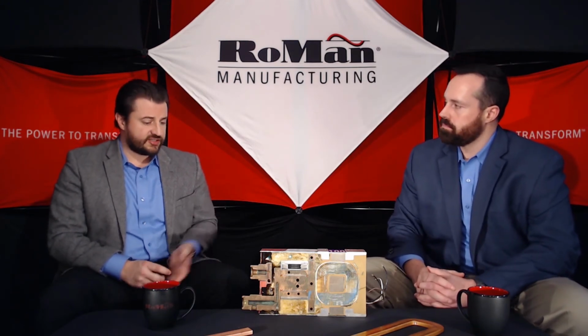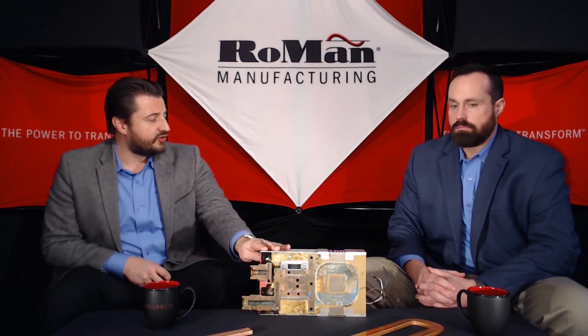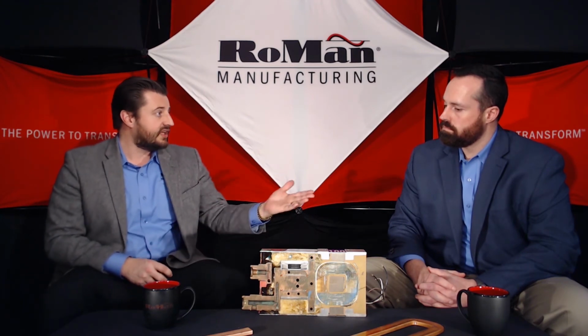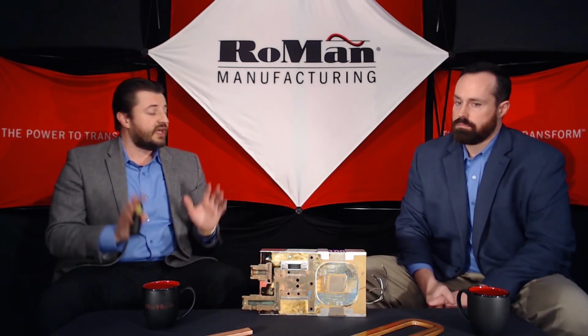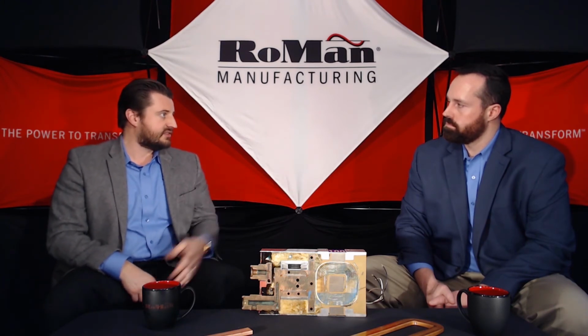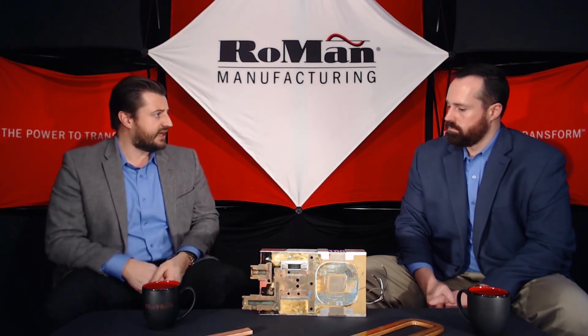Well, another consideration that pops into my mind is because this is totally enclosed, you're probably going to see a lot less maintenance on this transformer versus an air-cooled transformer, where the coils themselves are pretty much exposed to the elements, meaning you have to keep them clean so that they release heat. Yes, absolutely. I have a lot of customers that, when I tell them we use water-cooled transformers, are a little standoffish because in their minds water and electricity don't mix. How do you respond to that?